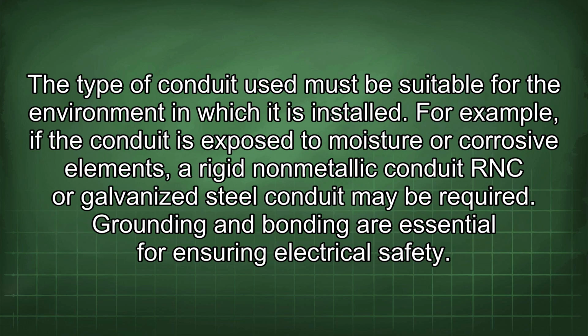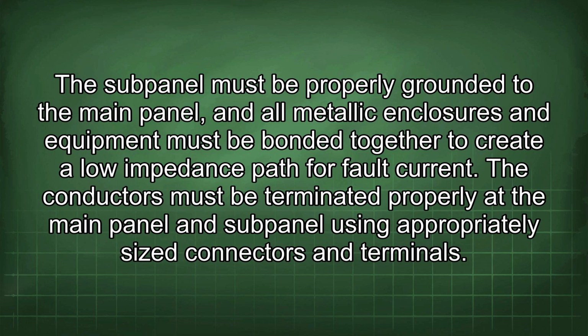The type of conduit used must be suitable for the environment in which it is installed. For example, if the conduit is exposed to moisture or corrosive elements, a rigid non-metallic conduit (RNC) or galvanized steel conduit may be required. Grounding and bonding are essential for ensuring electrical safety. The subpanel must be properly grounded to the main panel, and all metallic enclosures and equipment must be bonded together to create a low impedance path for fault current.